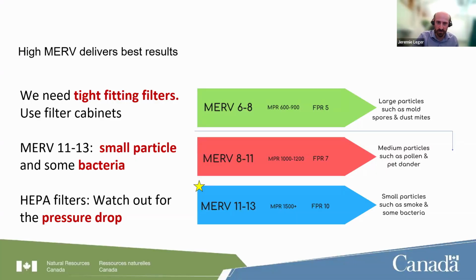But just having a filter alone is not going to get you there. You need tight fitting filters, so using a filter cabinet is very important here. You don't want the air to move around your filter, which is not very effective. You want the air to move through your filter. Making sure that you have a tight fitting filter using a filter cabinet is part of that retrofit design that you want to consider. You might have heard of HEPA filters as well. Essentially they move past the MERV 13. They're a higher efficiency filter, giving better filtration of bacteria and viruses.